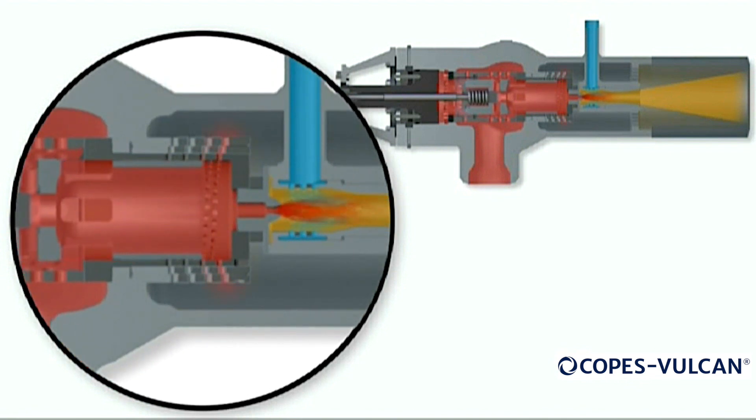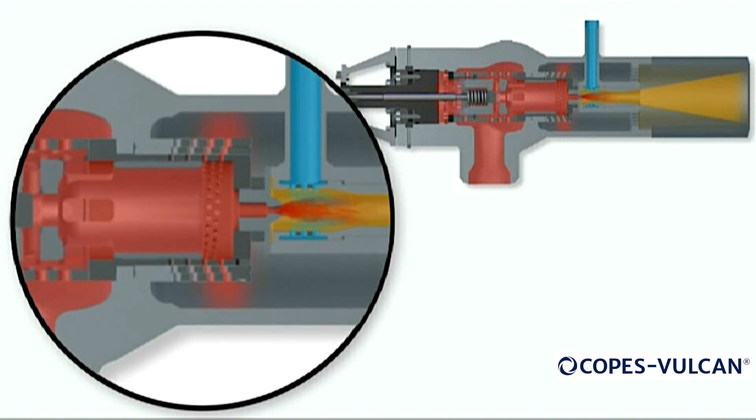As the main plug opens, steam first enters the valve via a heavy-duty distribution spacer. The steam passes through the spacer by means of numerous holes evenly positioned around the circumference. This heavy-duty distribution spacer has been specifically designed to negate any upstream pipework-induced flow disturbance being communicated to the main plug.